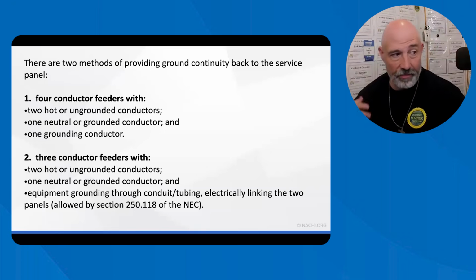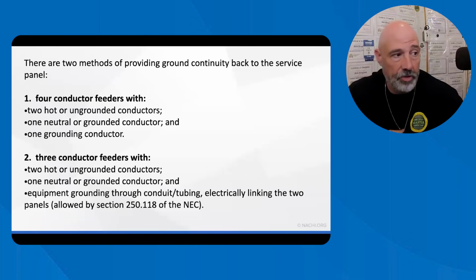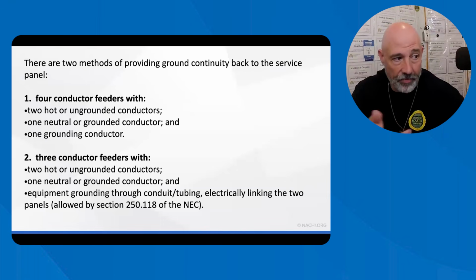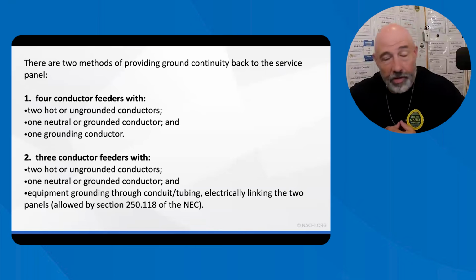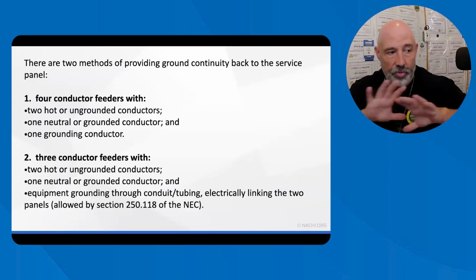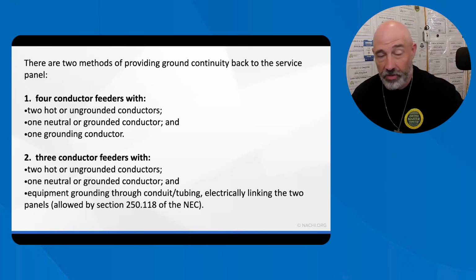So just be alert of this when you're calling things like this out. In any case whatsoever, make sure that you recommend further evaluation from an electrician if you're ever stuck on something. There are two paths for providing ground continuity back to the service panel. The 4-conductor feeders with 2 hots, ungrounded conductors, and 1 neutral and 1 grounding conductor, and the 3-conductor feeder. And this is all part of 250. Any grounding is in 250 of the NEC. So anytime you have any questions, go to 250.